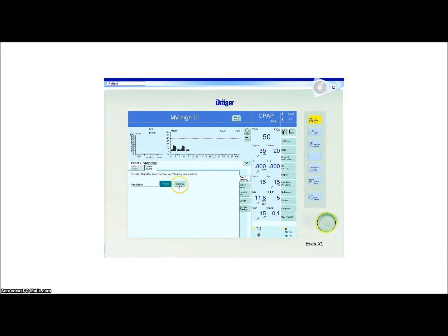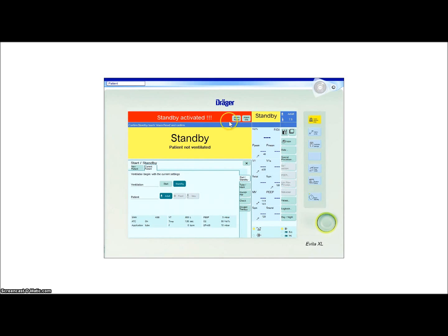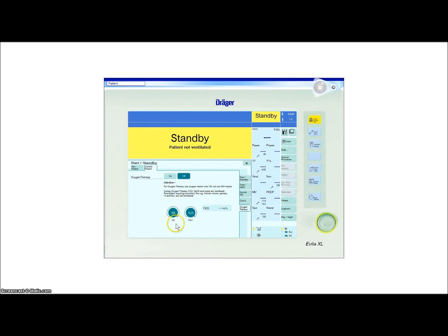We're going to hit standby. You will touch it since this is a touchscreen ventilator, and you will hit the rotary knob. So you get an alarm saying, "Oh, I'm in standby." Then we will confirm it by touching the alarm reset, and then hit alarm info. Or no, hit the rotary knob. Then we go to oxygen therapy down here. She could then set how much oxygen she wants to deliver. Do 40% at a flow of 40. And this is a simulation, so this is not, honestly, available, so I would just pretend.